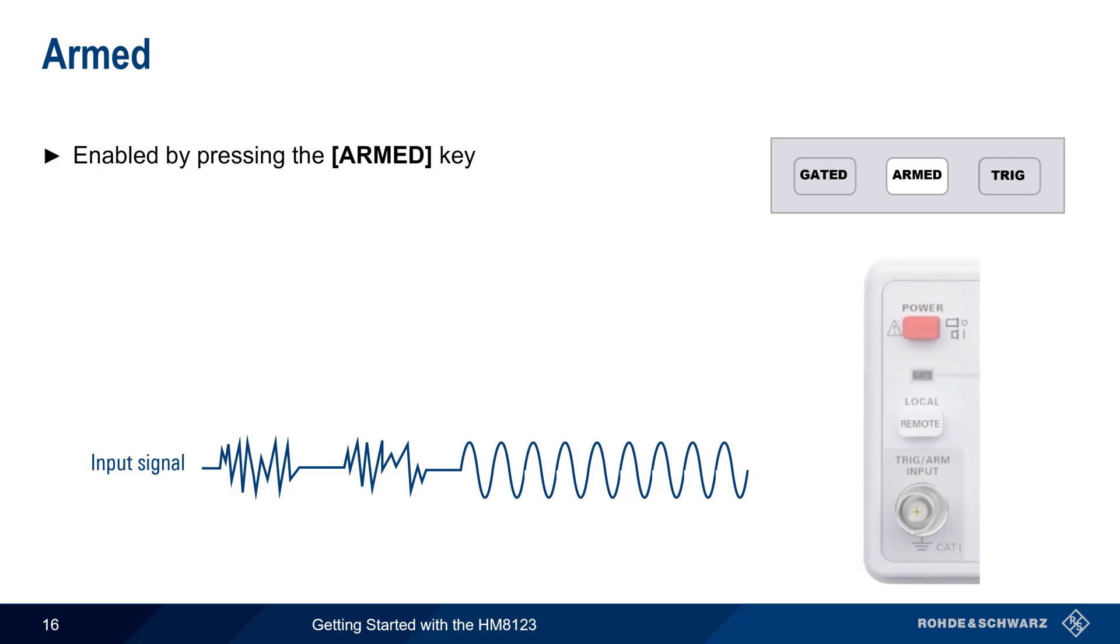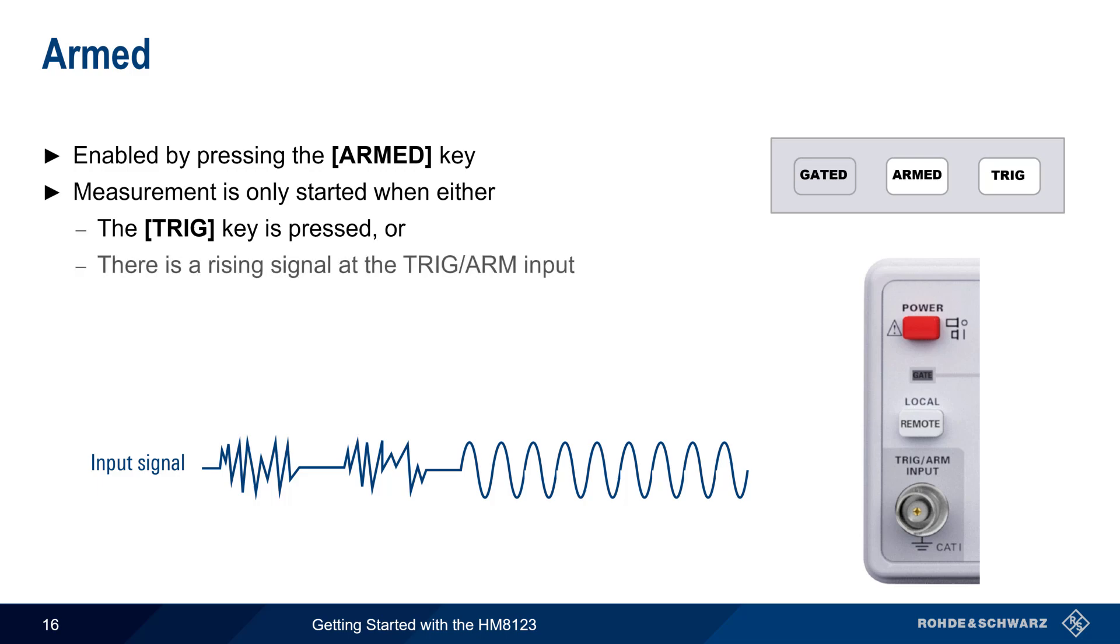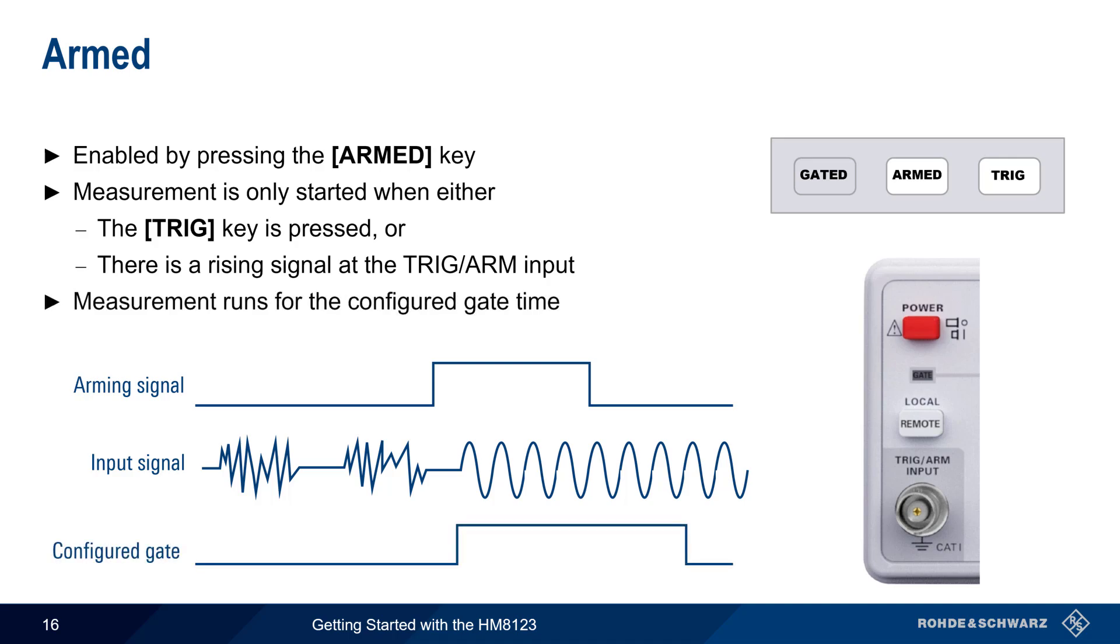The armed function is enabled by pressing the armed key, and this function helps prevent noise from triggering a measurement. Like Gated, it uses the external Trig Arm input on the front panel. When this mode is enabled, a measurement is only started when either the trigger key is pressed, or if there's a rising signal at the Trig Arm input. This arming signal, or trigger button press, then starts the measurement, which ends automatically at the end of the user configured gate time.